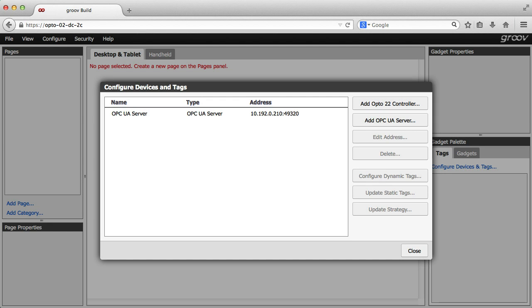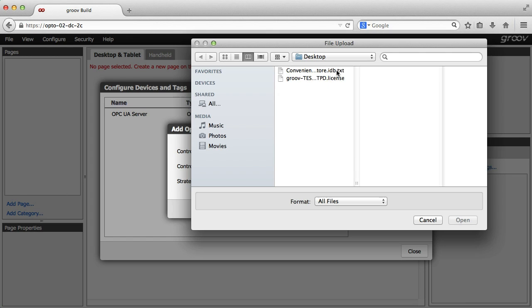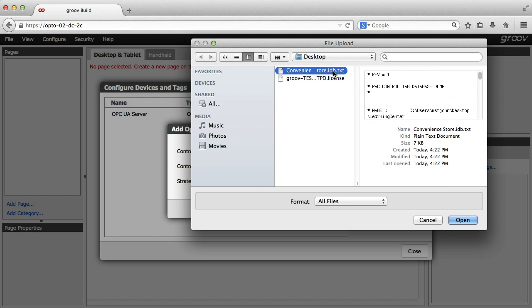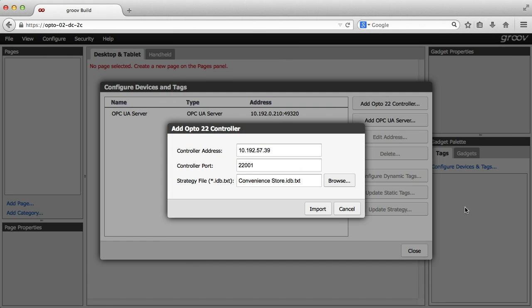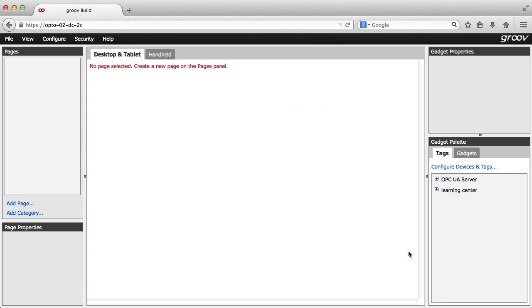To connect directly from groov to a PAC, click add Opto 22 controller. Type the controller's address, then browse to that controller's idb.txt file. This text file is generated by PAC control when you compile or download your strategy in the same folder as the strategy itself. I'll browse to a copy of that text file, then click import and close.